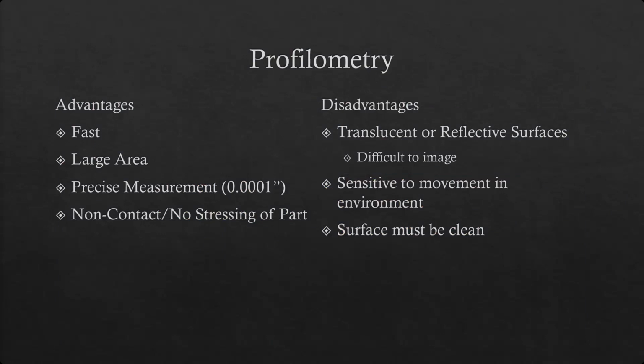Advantages of profilometry: it's very fast, and you can do a large area very quickly. This was for the purpose of dent mapping over a large area, and it was very beneficial. It made the process much quicker. Here, I talk about the ones you saw there for surface treatment, to the 10,000th of an inch. The ones we would use in aviation, you sacrifice some of that precision, going to the 100th or 1000th of an inch, but scan a much larger area much more quickly. And again, no contact, no stressing of the part, so there's very little chance of causing any kind of damage.